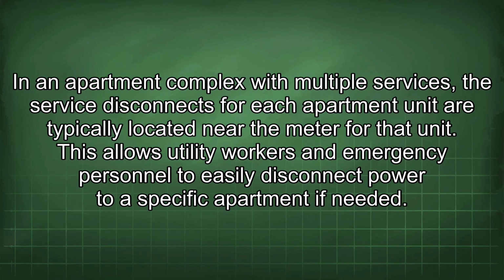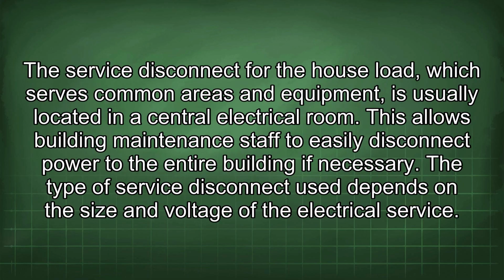In an apartment complex with multiple services, the service disconnects for each apartment unit are typically located near the meter for the unit. This allows utility workers and emergency personnel to easily disconnect power to a specific apartment if needed. The service disconnect for the house load, which serves common areas and equipment, is usually located in a central electrical room. This allows building maintenance staff to easily disconnect power to the entire building if necessary.